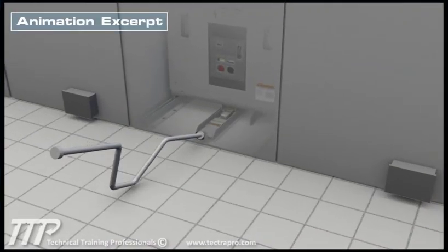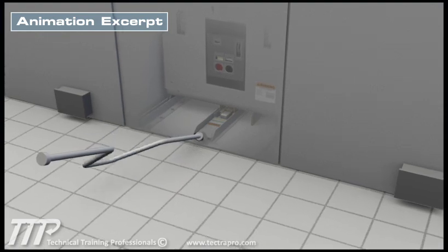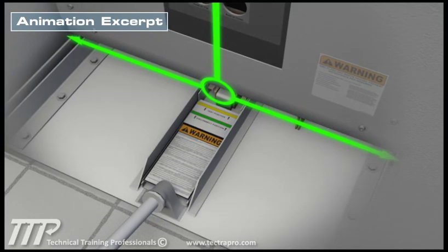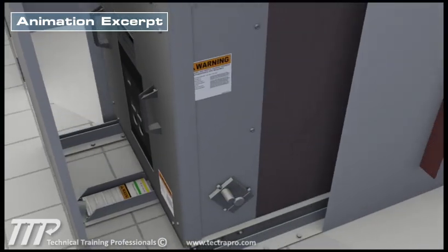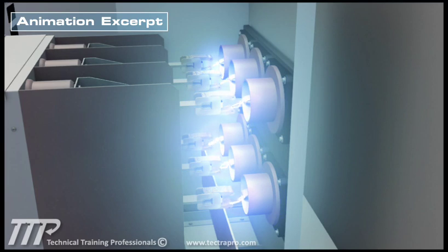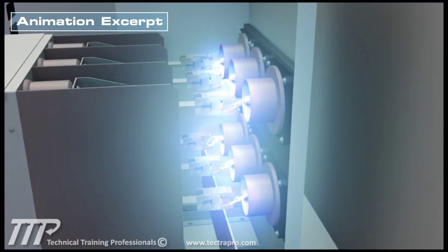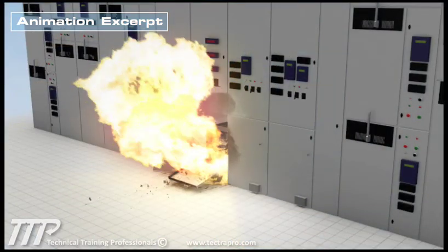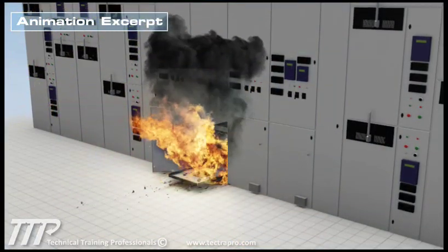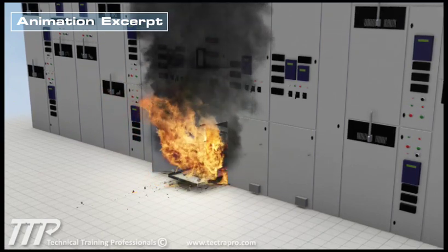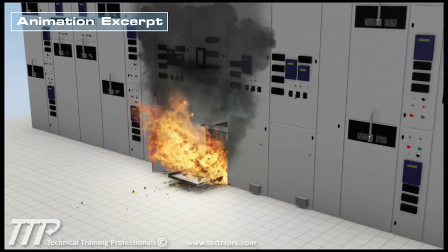Once the action of removing the circuit breaker is started, it must not be stopped until the handle reaches, at a minimum, the test position. If the removal of the circuit breaker is stopped mid-travel, it can cause arcing in the gear and damage the circuit breaker or switch gear and result in a catastrophic arc flash event. Refer to plant arc blast policies and posted arc flash labels for proper PPE during the rack out event.